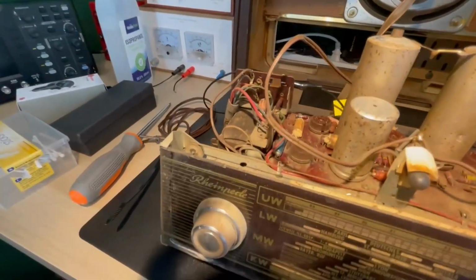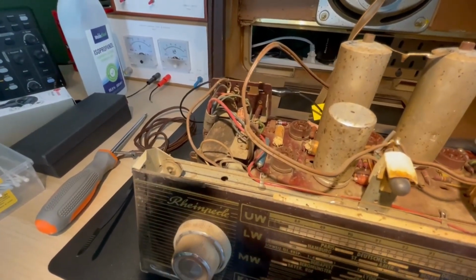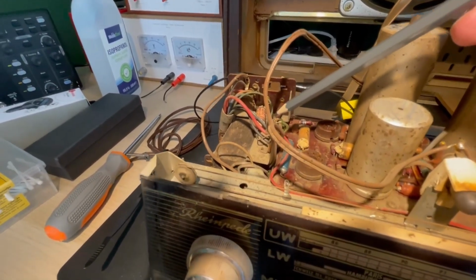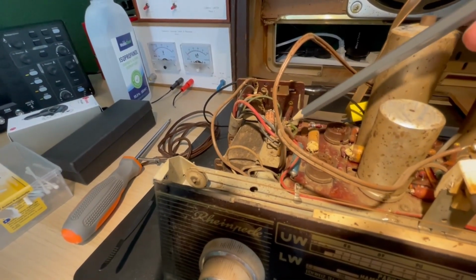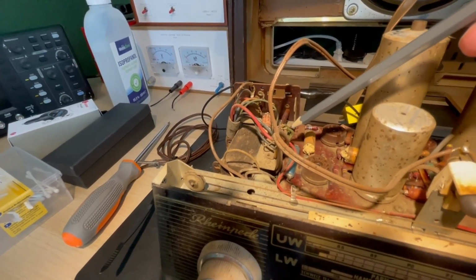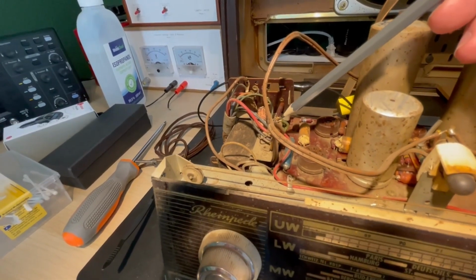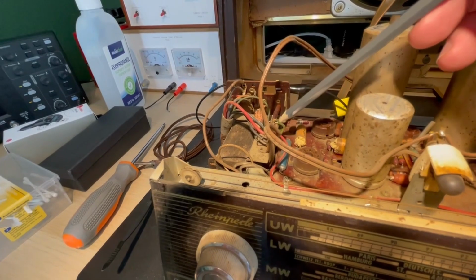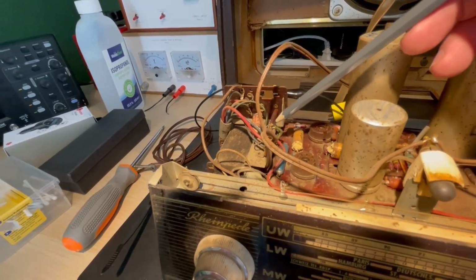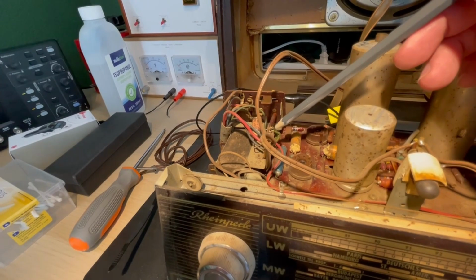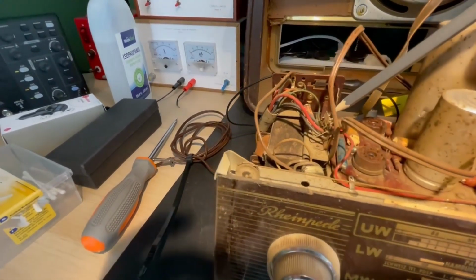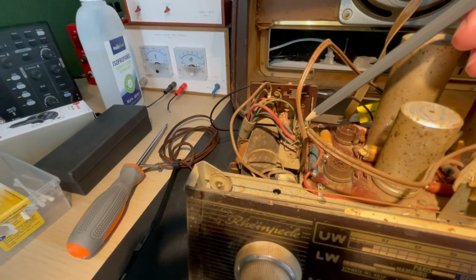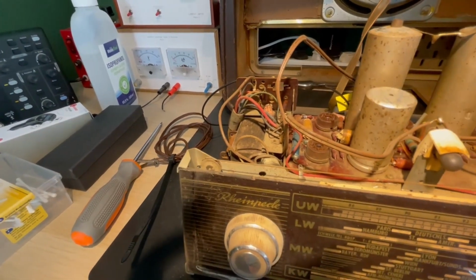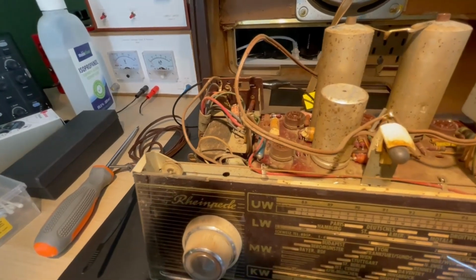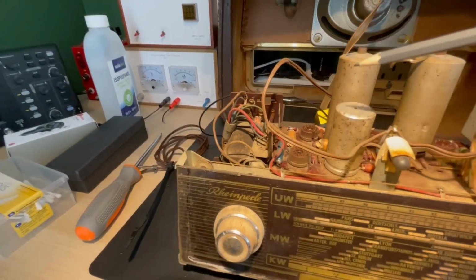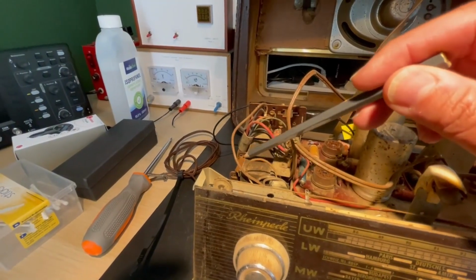So this is where the secondary goes into the selenium rectifier that's under this board. These two wires here are the secondary windings with 200 plus volts. What I plan doing is disconnect one of these wires, so we're basically not powering the selenium rectifier, not powering anything here. All we would be doing is running tension.